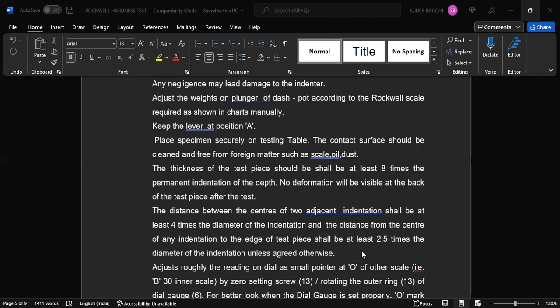Now adjust roughly the dial of the machine, with the small pointer at O on the other side. What we'll do is place the test piece over the table. We have to place the indenter in the proper place, properly selected and fixed on the work. Next, the platform should be raised by rotating the handle clockwise, so that it goes up and touches the bottom of the indenter.